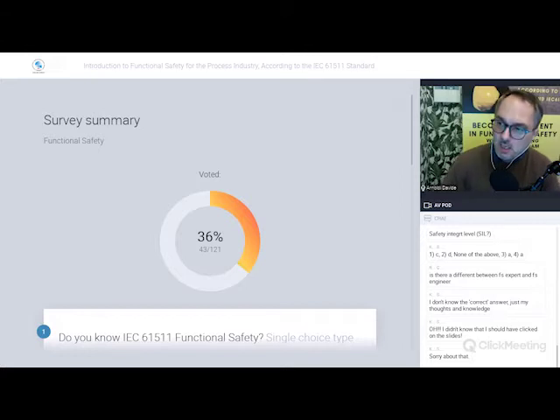This is just, let me say, bad information from the manufacturer of devices. Safety integrity level is applicable only to the safety loop, where the safety loop is composed of sensor, logic solver, and final elements. The third question was, does your company apply HAZOP type risk assessment studies? I was sure that a good percentage of your company know about HAZOP.